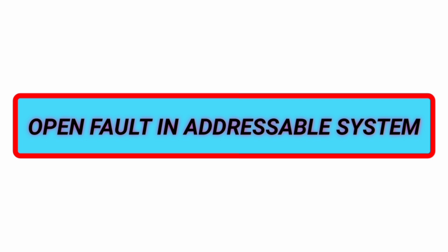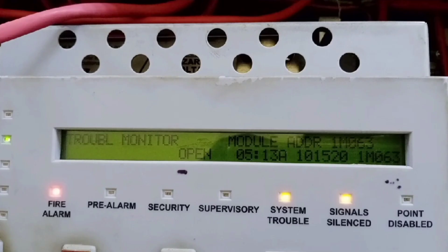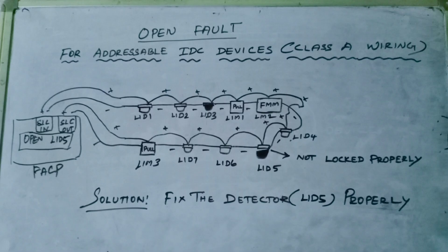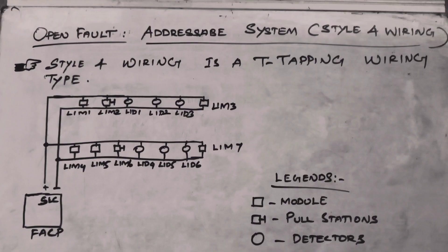Now, for finding the open trouble in an addressable system, it is much easier to find. It will show the address and location as per your program. You can go to that place and fix the detector, pull station, or module properly — it's a piece of cake. As I explained in class wiring, here you have a T-tap wiring design, and here we have NAC devices with open fault in Class B wiring.